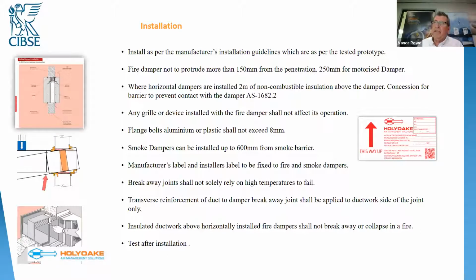A little bit about installation. I'm not really going to, again, spend too much time on that, just with the audience that we're talking about today. But a couple of things to think about, particularly when we're specifying dampers. Obviously, smoke dampers can now be installed up to 600 millimeters from the smoke barrier. It's critical that manufacturers' labels and installers' labels are fixed to fire and smoke dampers.